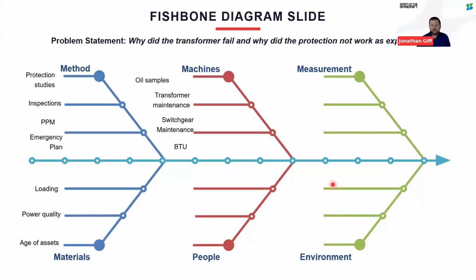I think we covered most there, but really just for our audience, an important part with maintenance, especially being a duty holder, is that when you do receive maintenance check sheets from the technicians, from the electrical fitters who were carrying out the work, you have some process to collect that data, analyze that data, and look for trends. So looking at historic oil samples or maintenance records, was there anything in there that flagged up that the transformer was starting to degrade, or that the switchgear, sorry, may not operate? Was there anything in the historical data that would suggest that?